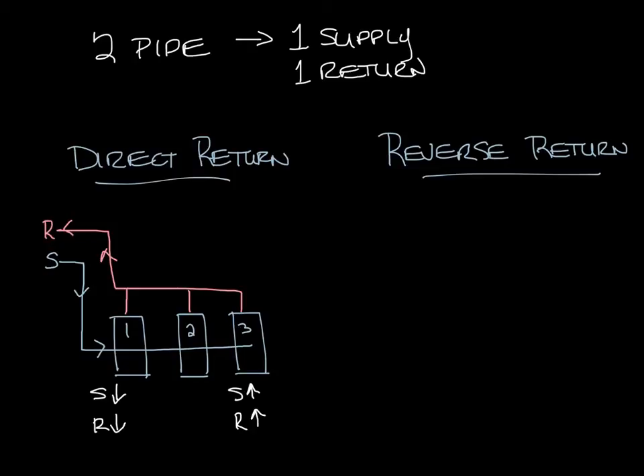So looking at this you can see that the loss going through the first unit through the supply and up into the return is going to be the lowest. So during low flow conditions most of the water will want to go through the first unit.